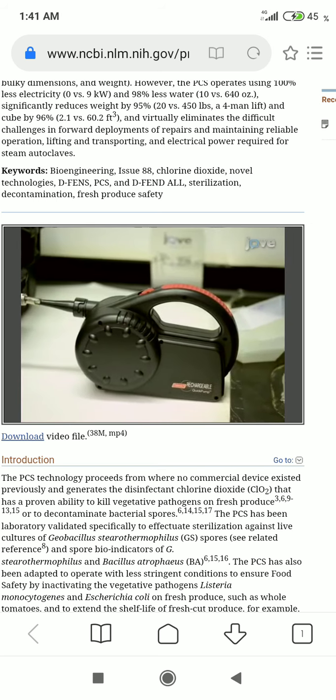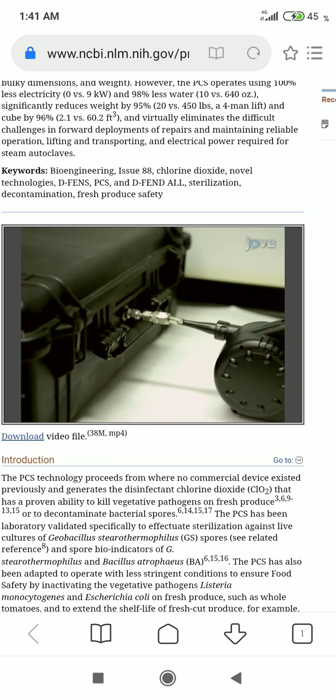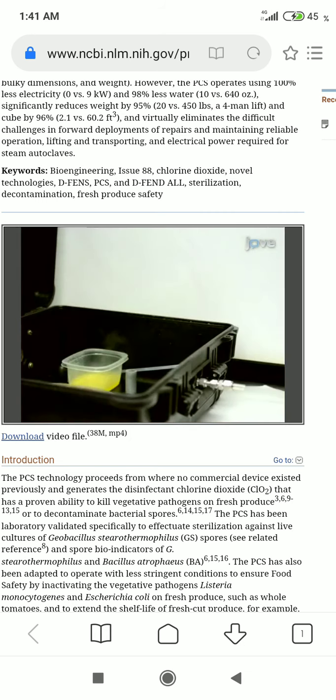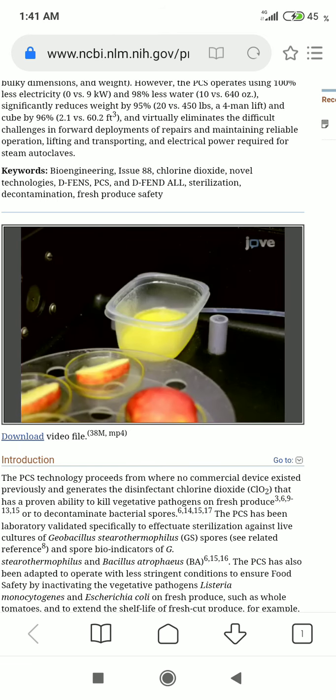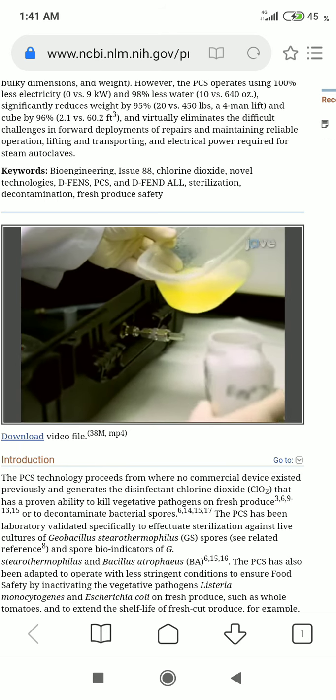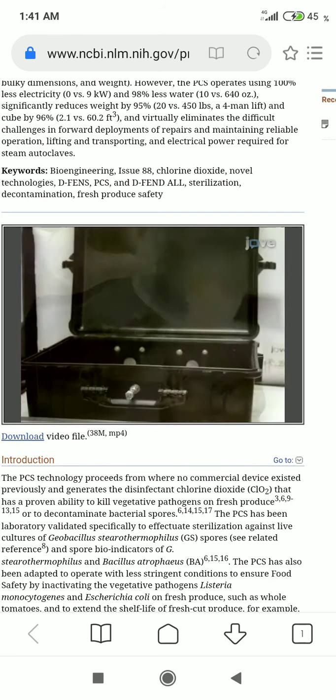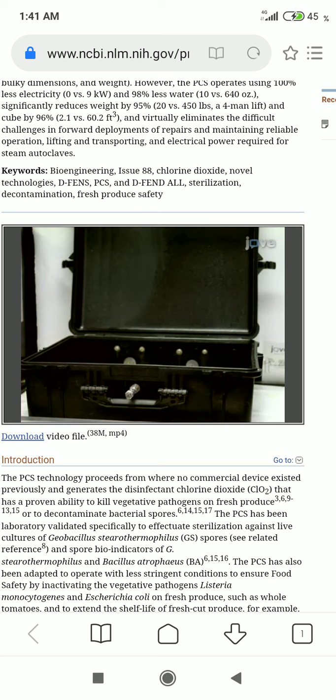At 25 minutes, connect a battery-operated air pump or hand pump to the filtered inlet valve to pump air through the chamber. After 5 minutes, stop the air flushing, open the case, and remove treated items. The reaction vessel contains benign chemical salts in water that are easily disposed of.